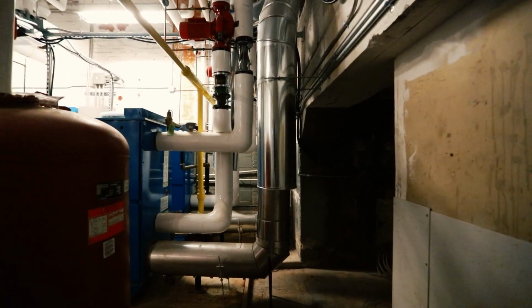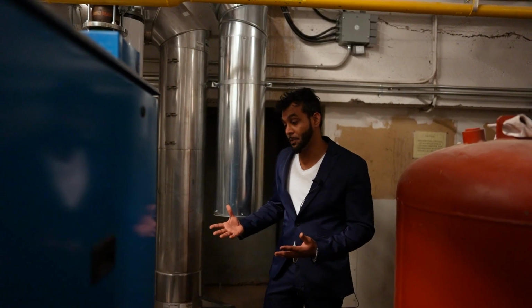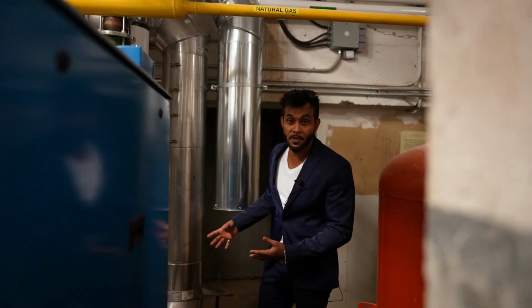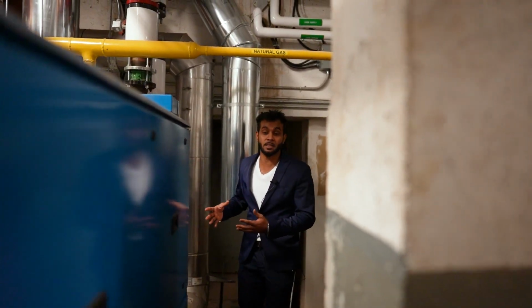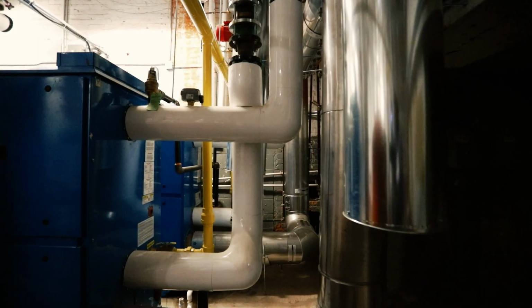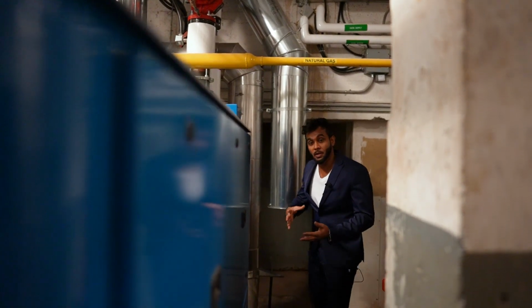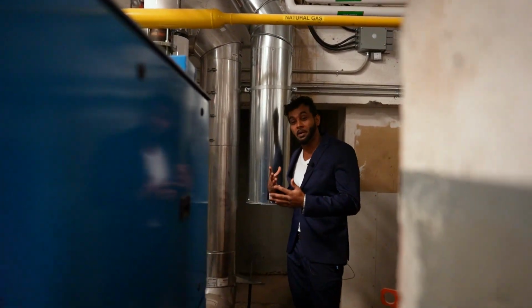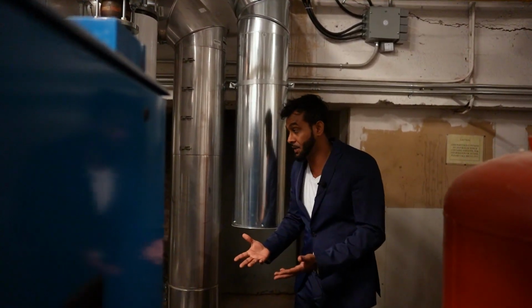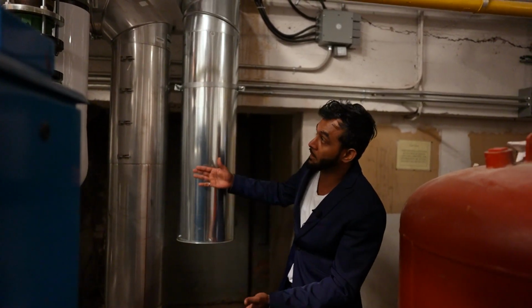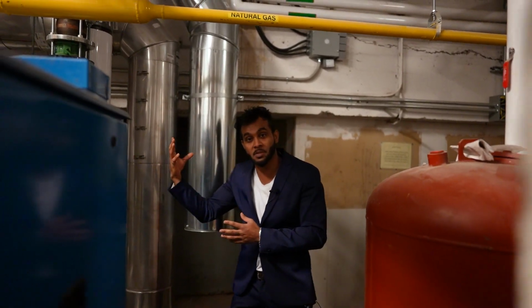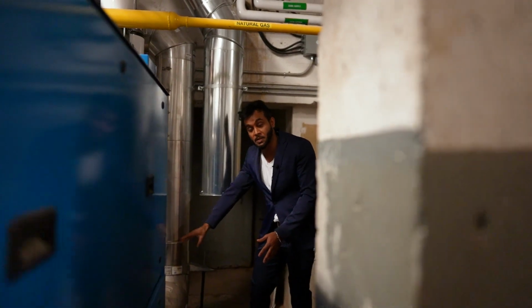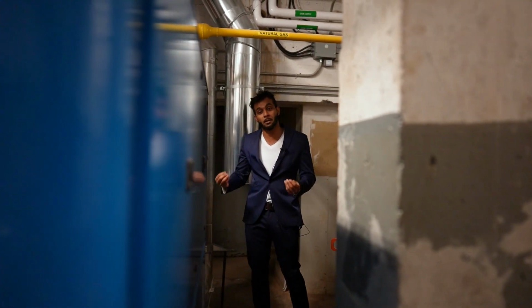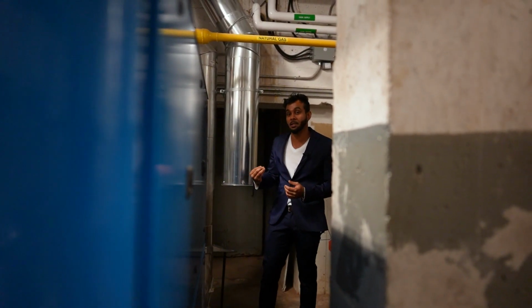Behind the boilers, one of the greatest challenges we had was running the venting, because both vents come into one chimney and go all the way to the roof. We had to do a lot of work with the guys, working tirelessly to get this venting properly done, with the proper slope and proper drainage, to make sure the boiler works at its best capacity.